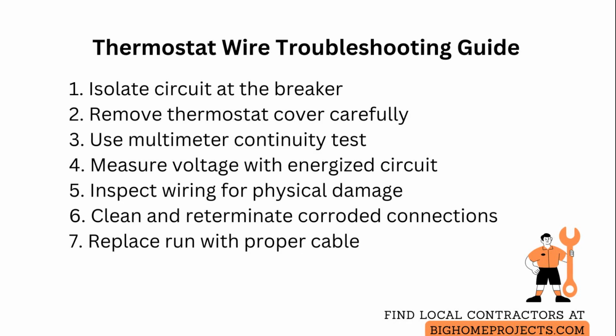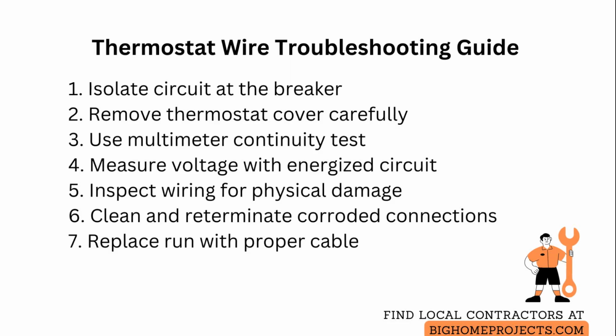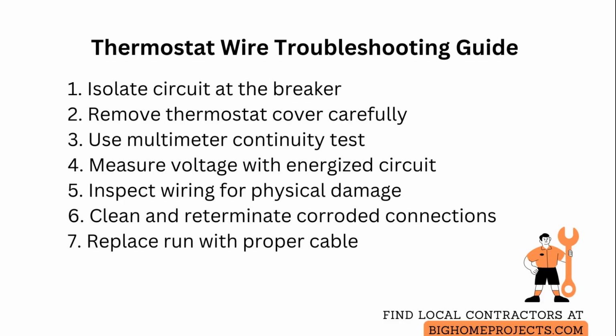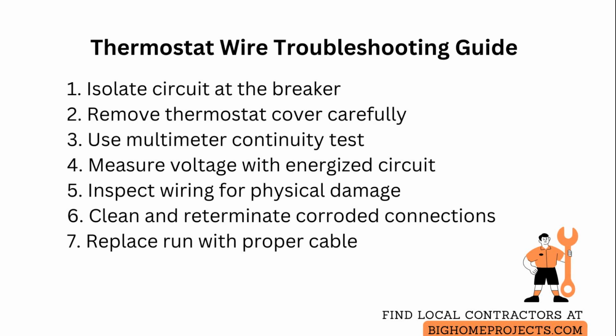Remove the screw, clean the conductor with fine sandpaper, and reterminate with a secure wrap or crimped ferrule to restore reliable contact. If the wire is found open, replace the run using thermostat cable rated for the application, typically 5-conductor 24-volt control cable for modern systems, and route it away from high-voltage lines and moving parts to prevent future damage.